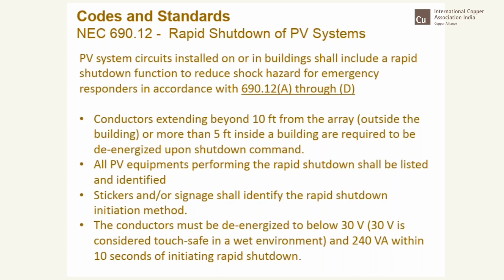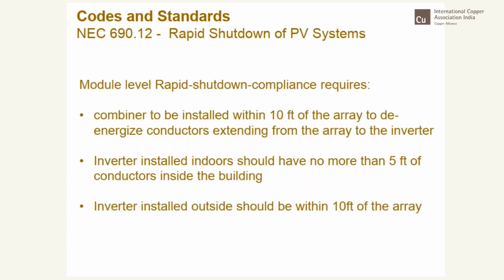So the moment you find that there is some issue and you shut down the inverter, a series of shutting down should happen, so that you shut down the generation up to the module level. So you avoid any flow of current in the circuit and the possibility of shorts, making the metal contacts live or giving rise to a fire. So stickers and signages all should be provided. The conductors must be de-energized to below 30 volts. Okay, so then you can go up to the module level rapid shutdown.